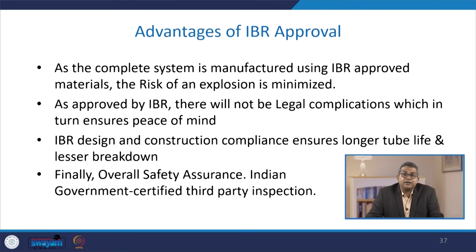The IBR design and construction compliance ensures longer tube life and fewer breakdowns, because sometimes, because of repeated use, scale formation, and sometimes corrosive material involvement, the tube may become brittle or deformed, and that may create a problem and lead to boiler explosion. So IBR approval is essential with respect to design and construction. For overall safety assurance, the Indian government certifies third party inspection under the aegis of IBR.